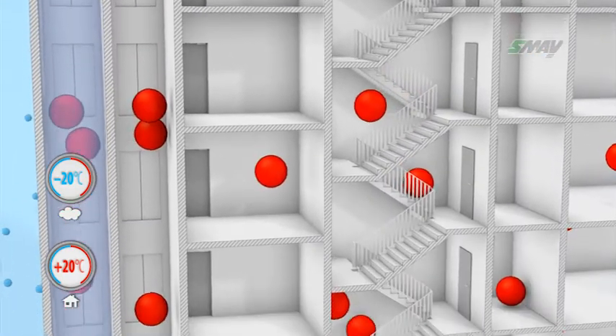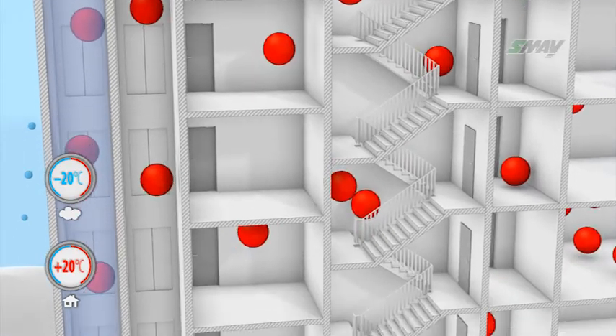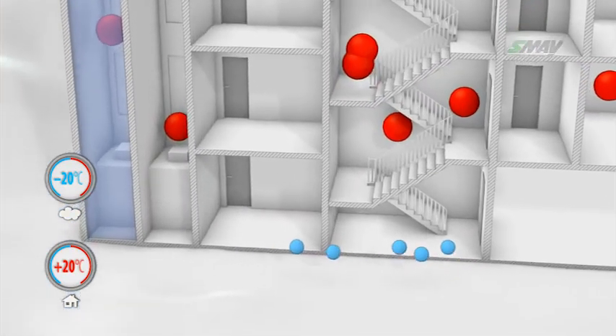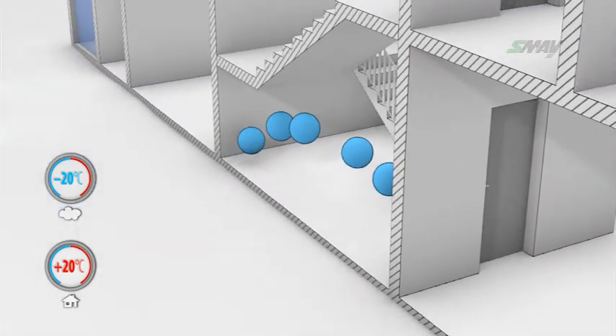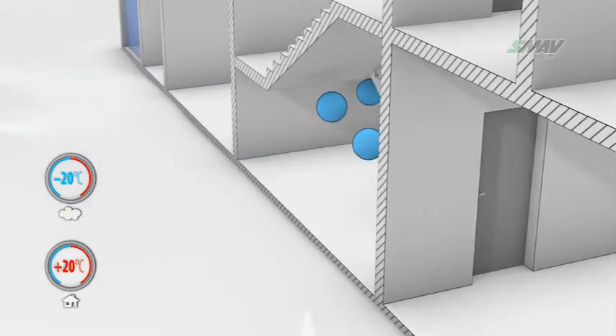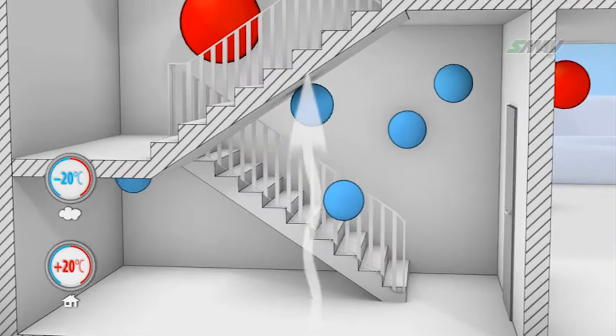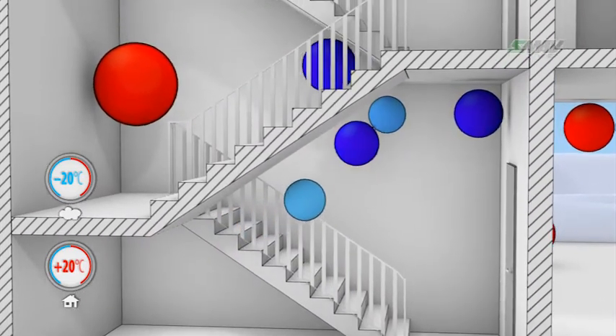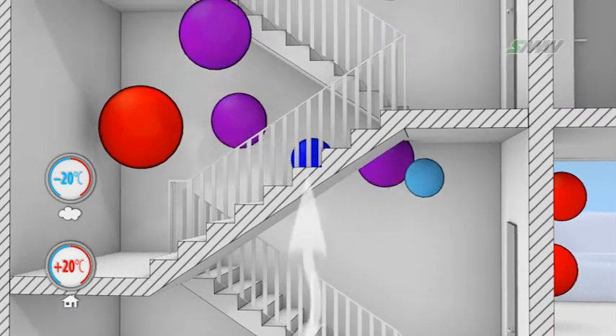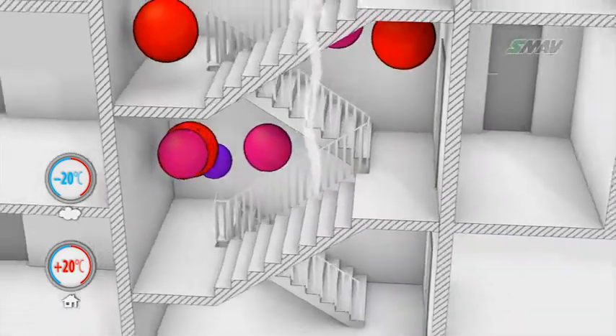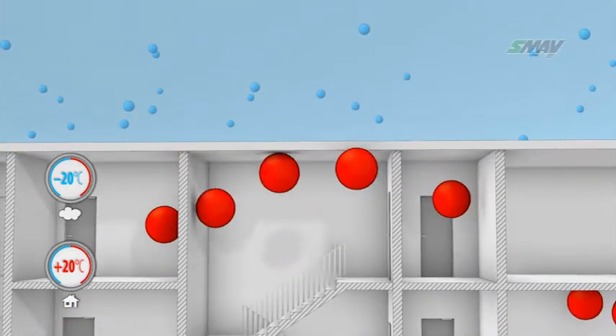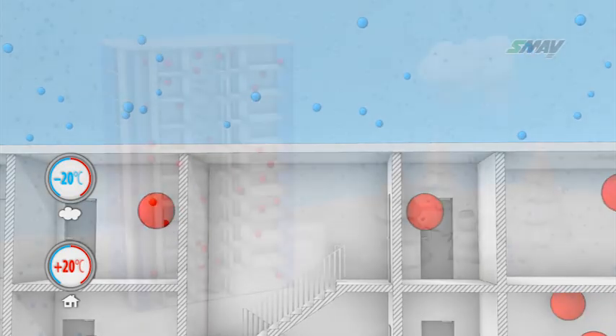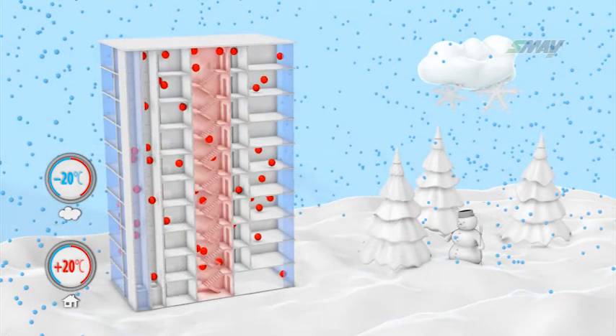Differences in density significantly affect pressure distribution in buildings. In winter, ambient air gets into the stairwell and because of buoyancy it rises, causing a differentiation in pressure inside its volume. If the stairwell is not airtight, or a window or doors are open at the building entrance level, the stack effect will always occur if there is a difference in the air temperature between the stairwell and outside.